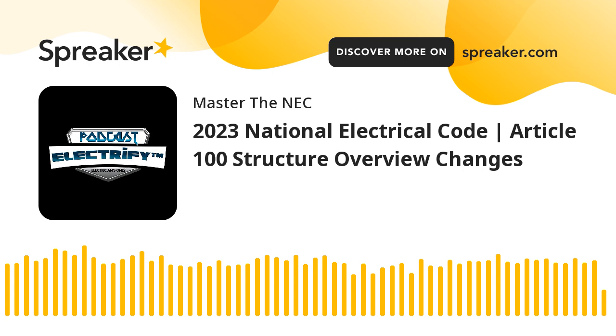All right, so Article 100 has been radically changed for the 2023 edition of the National Electrical Code. For those of you in the 2020, you know that throughout the code, there was this reference to .2 sections, and that was actually in the scope of Article 100. It said definitions are also found in the .2 section of other articles. Now, .2 is referencing section 2, section 3, section 4, that would be .2, .3, .4 of a specific article, like non-metallic sheath cable, Article 334, things like that. So the .2 had additional definitions, but they were germane only to that specific article.